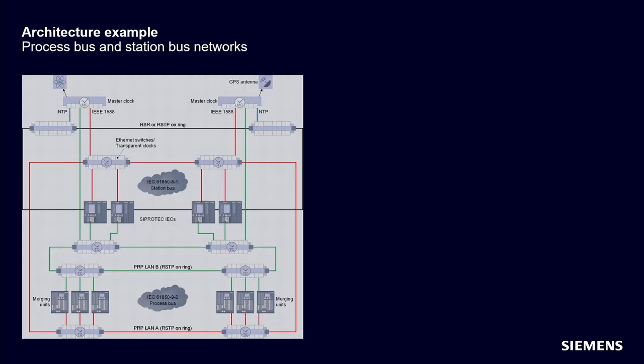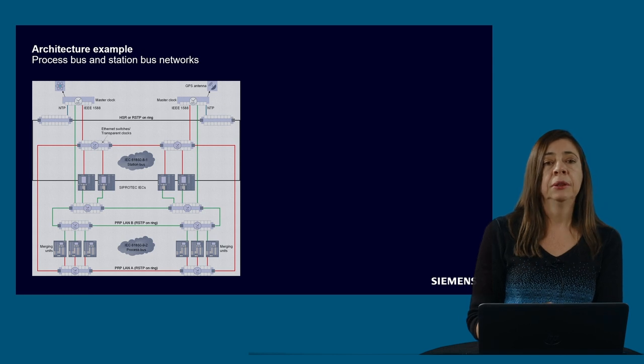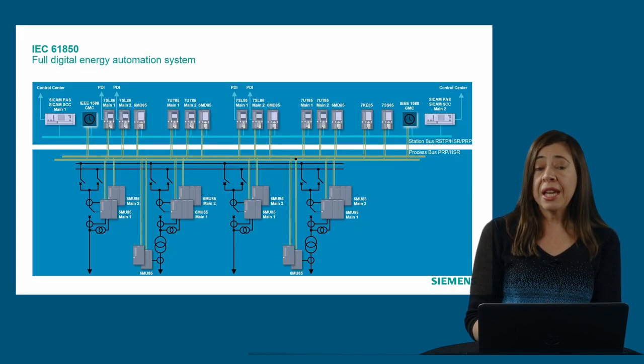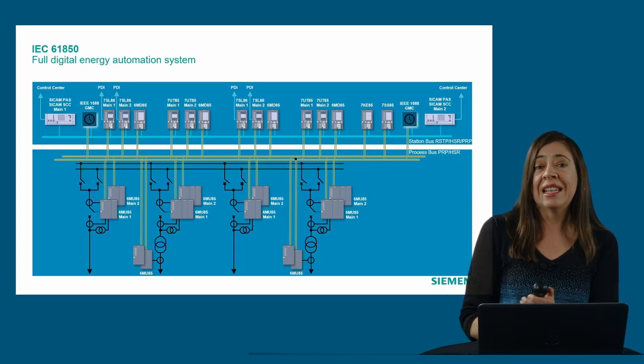If we extend this configuration with a station bus, then you see here the device is also connected to this black network. The station bus is completely independent. It can be RSTP, HSR, or PRP, depending on the need of the project. And here we are also using the same master clocks to feed NTP signals into the station bus. So here we can also see the primary part.